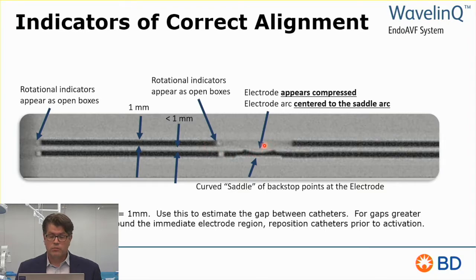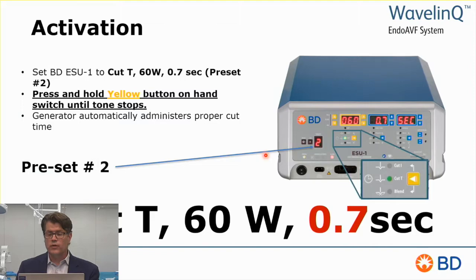Once again, the electrode, as you move the arterial catheter back and forth, you see a little mild compression of it, knowing that you're in the correct location. You check all these, of course, before activating or firing it, just to make sure we're in good position. The Bovi itself is 60 watts for 0.7 seconds. It's a preset. You press and hold down the yellow button, very simple, it activates and then turns itself off for you.